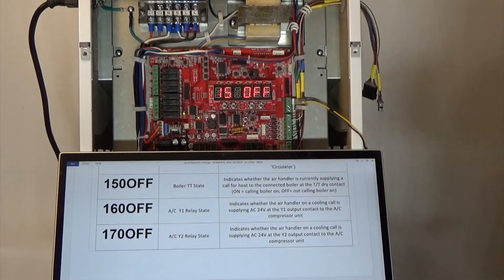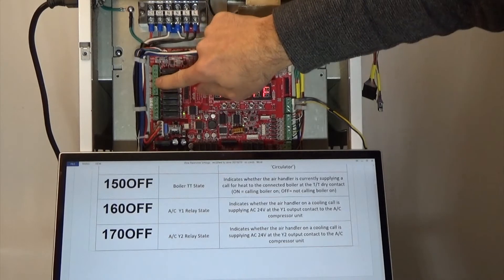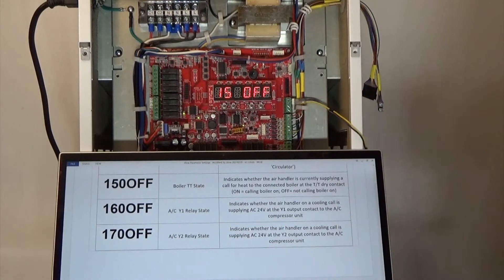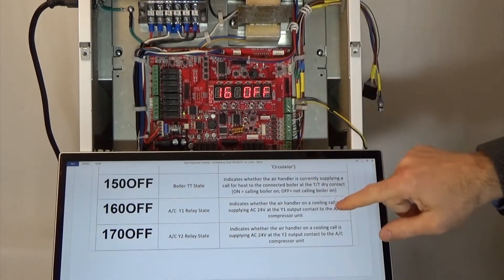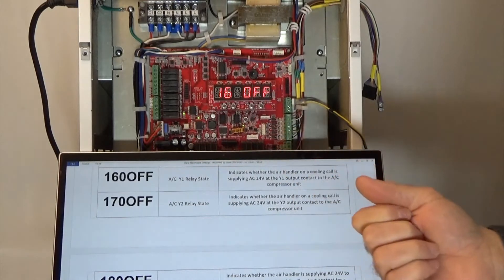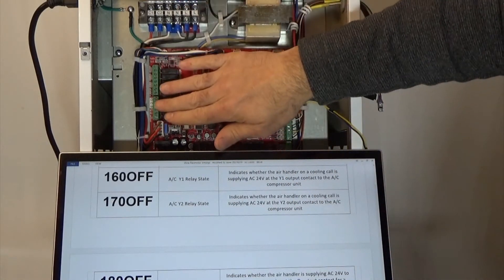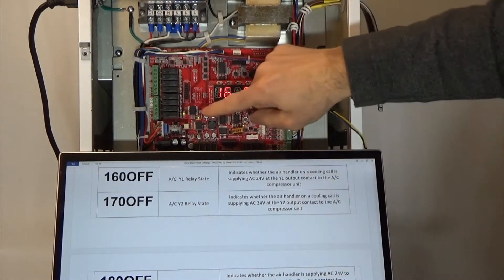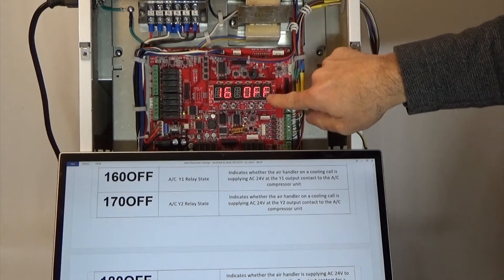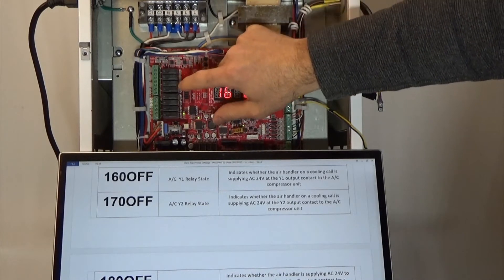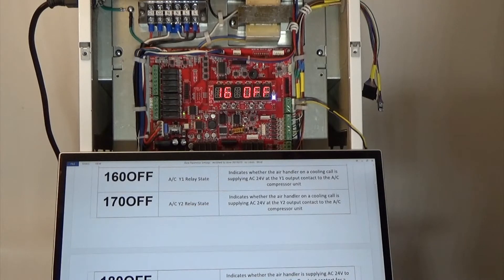Parameter number 15 is the boiler TT state — are we calling the boiler on at the TT connection, sending a call for the boiler through that dry contact? Parameter number 16 is the same type of thing — are we supplying a call for cooling at the ACY1 relay? We have outputs for the AC compressor. Are we sending 24 volts there or not? Right now it's off. If it was on, you would see the LED light on the other side of that relay illuminated, confirming it is being called on.